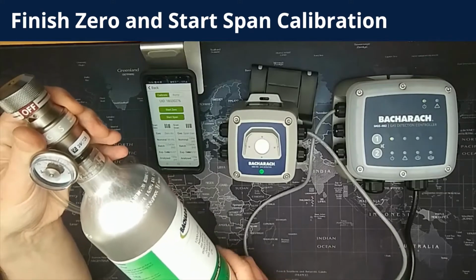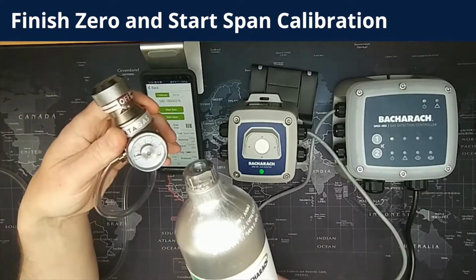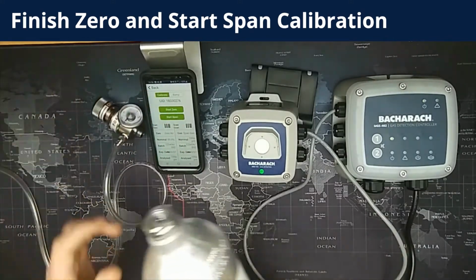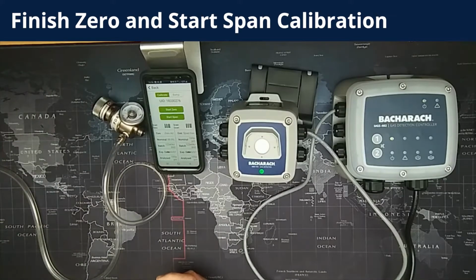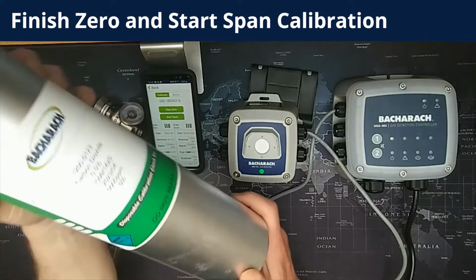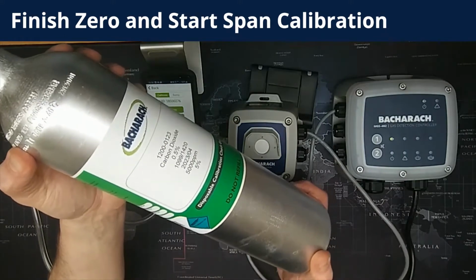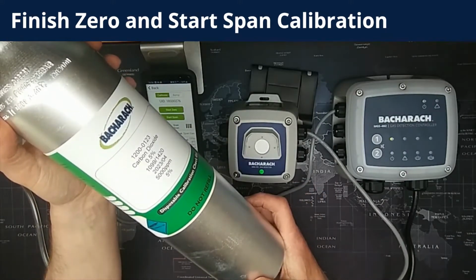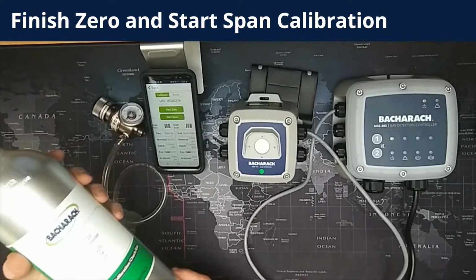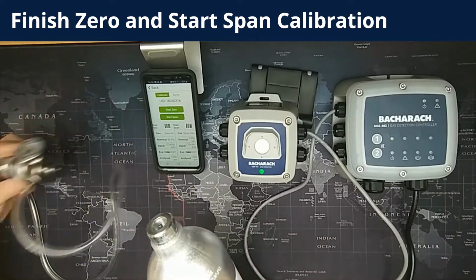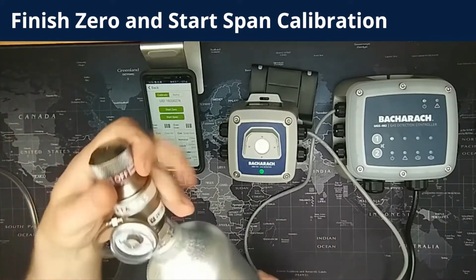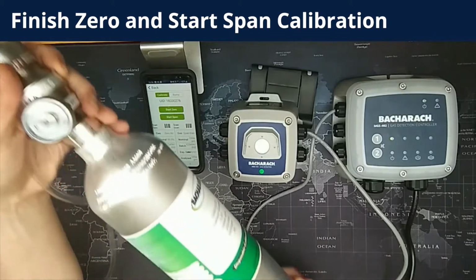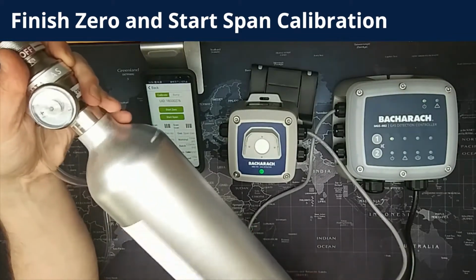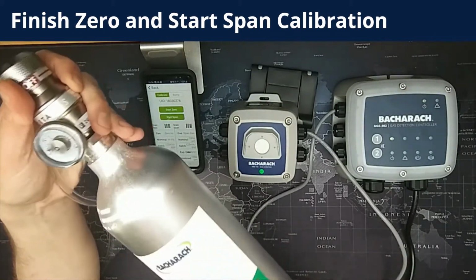You can now swap the gas bottles over from the 0 to the span gas. So you remove the 0 gas cylinder. So that's the cylinder off the regulator. You now get your calibration gas, which is the required concentration. This is also detailed in the manuals. And then you fit that to the regulator.